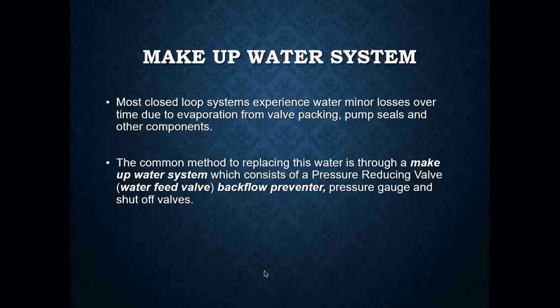Most closed-loop systems experience water loss over time through evaporation, from valve packings, pump seals, and other components. We need some way to make up that lost water. The common method is through a make-up water valve or make-up water system, which consists of a pressure reducing valve — better known as your water feed valve — a backflow preventer, a pressure gauge, and a shut-off valve.